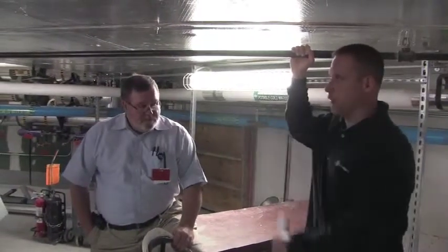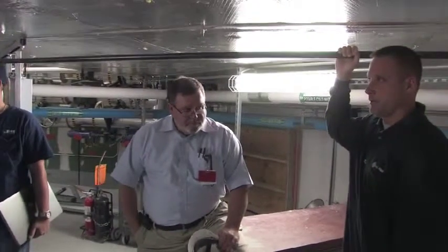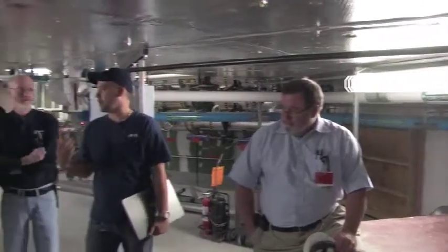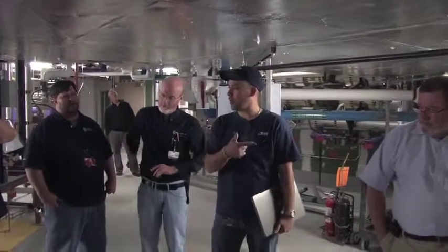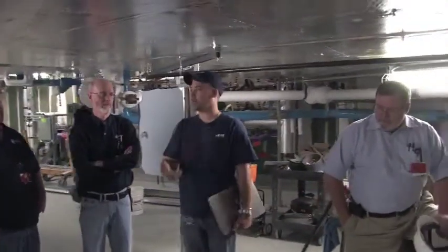There's the same unit. Oh, okay. So there's 3 of these. They're all the same size. The only difference between that one and these ones is these ones shut off on temperature. The one downstairs constantly circulates the air in the electric room. So these ones will come on when it goes above set point. The ones down there, the fan will continue to run.